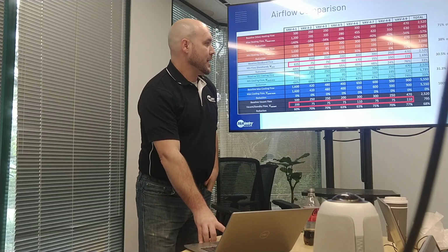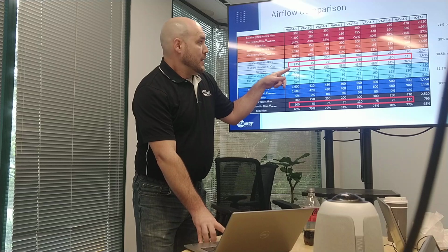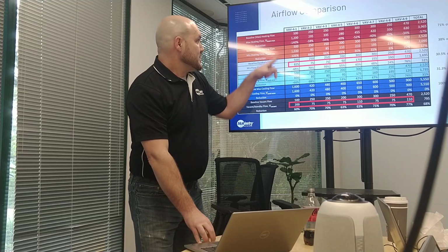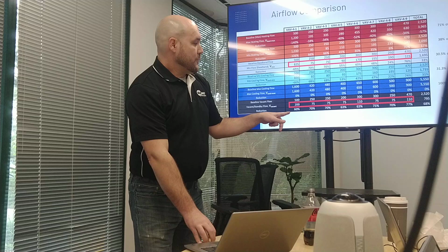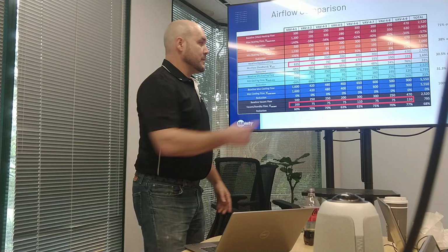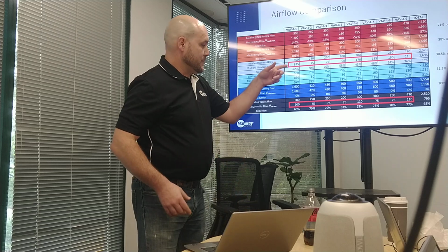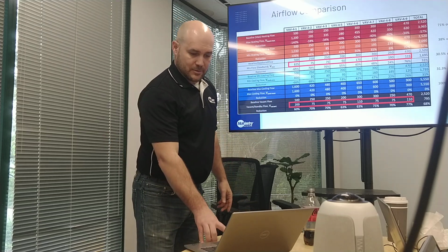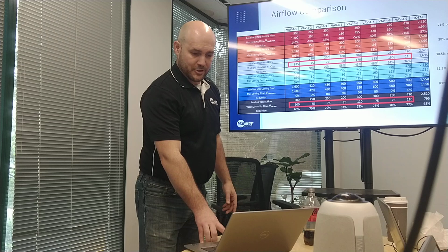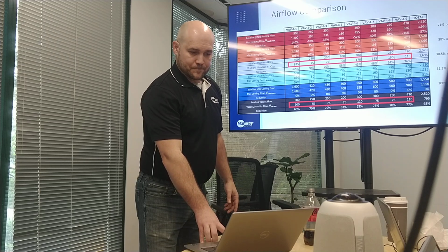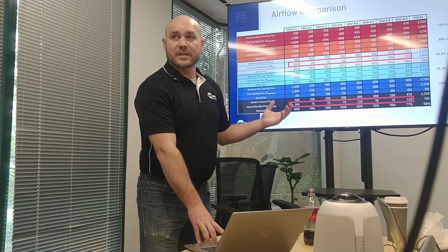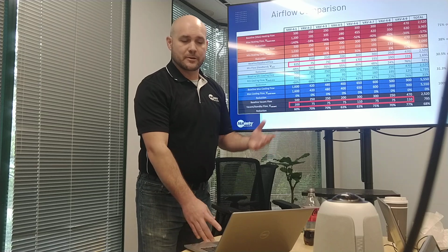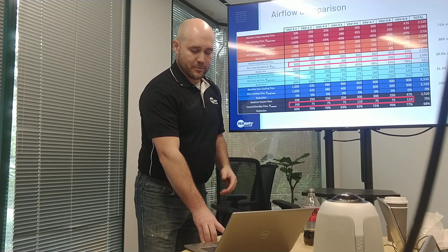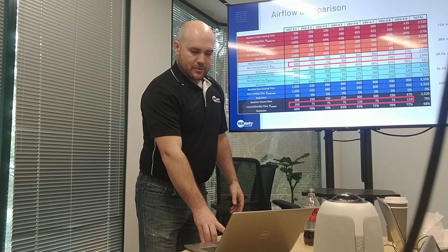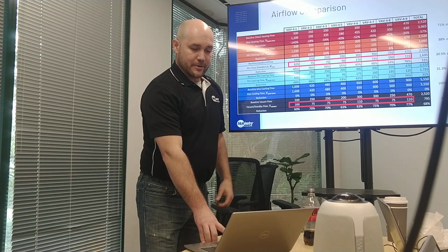So yeah, and that'll tell you, well, the one that has the biggest reduction is this lecture hall VAV41. If you only had the budget to install one occupancy sensor, that would be where you want to do it, because the difference between these boxes is the largest there. There could be other inputs like how often that space is used versus maybe other spaces that are used a lot more or less frequently. So don't let that be your only guide, but that can inform a whole lot.